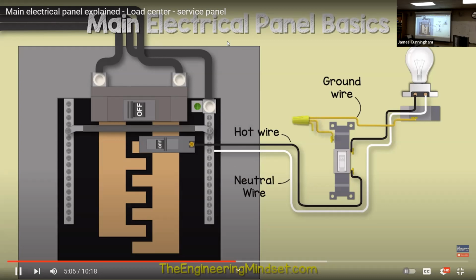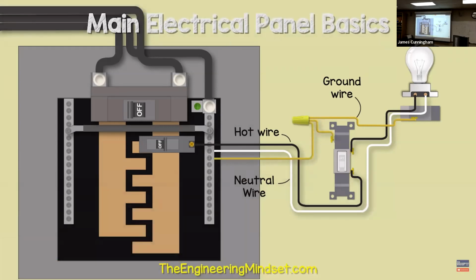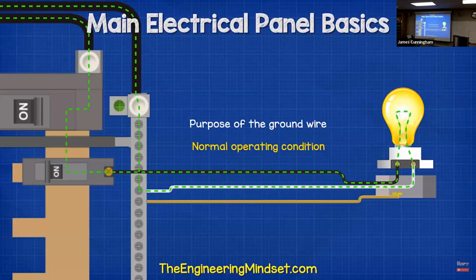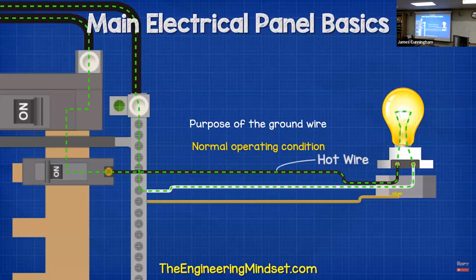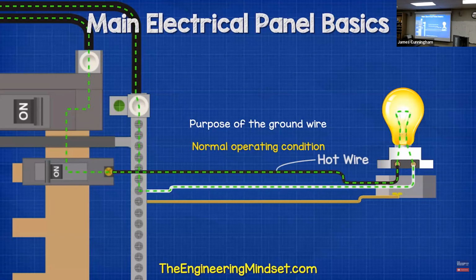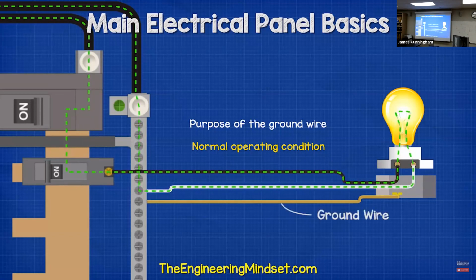Wire from the metal casing of the ceiling box and the switch, and we also join this to the neutral bus bar, as in this case it's shared. The purpose of the hot wire is to carry the electrical current over to the light fitting. The purpose of the neutral wire is to carry the used electrical current back to the main panel and then back to the transformer. The purpose of the ground wire is to provide protection for a fault current.